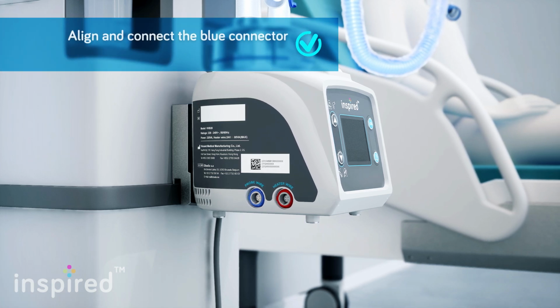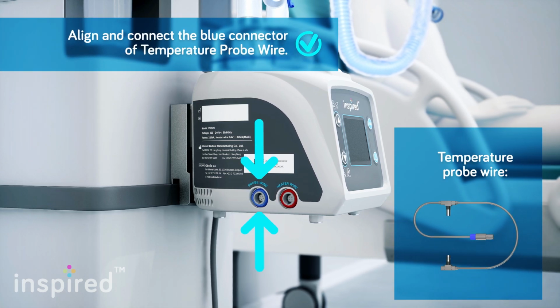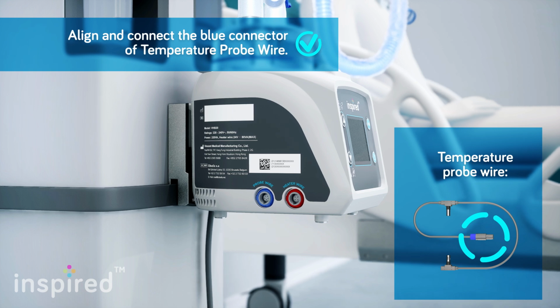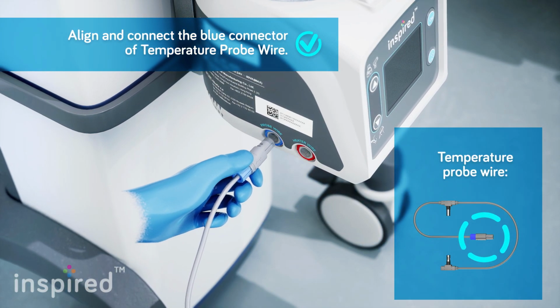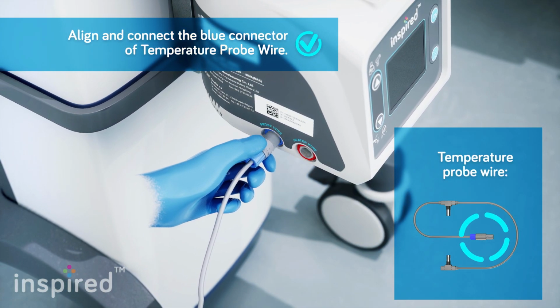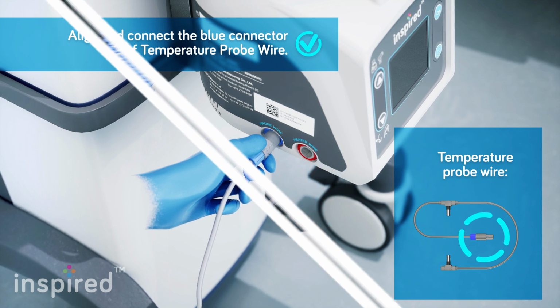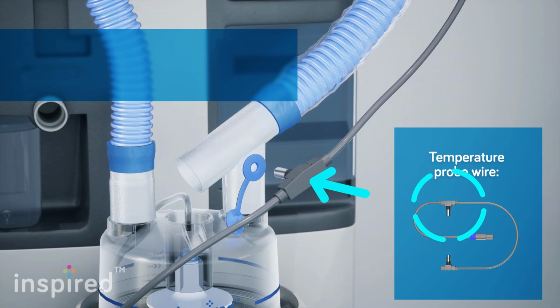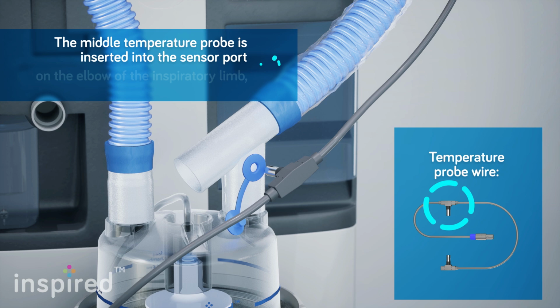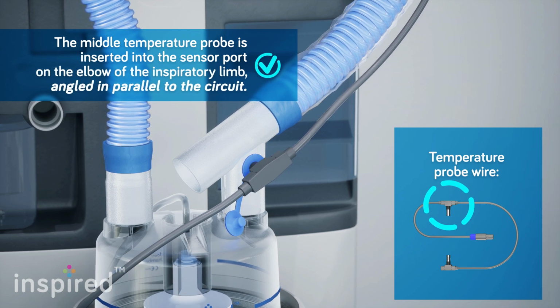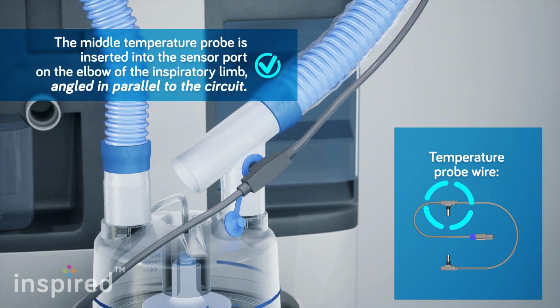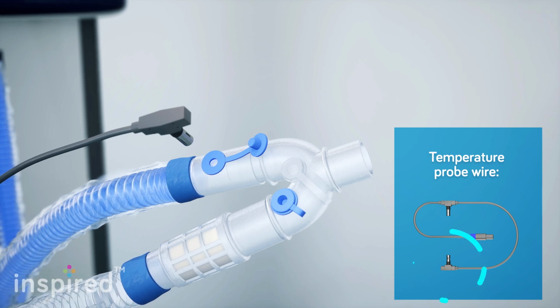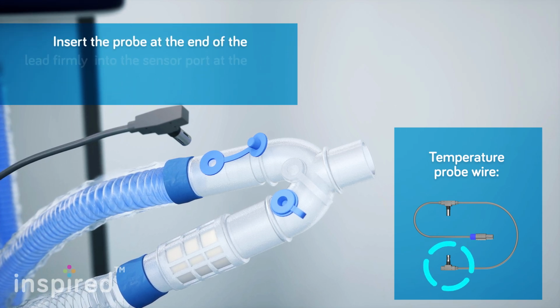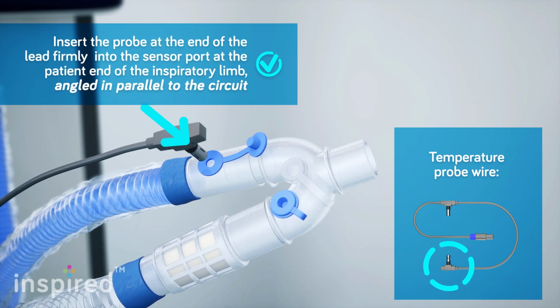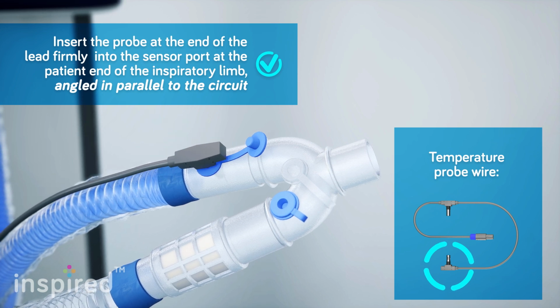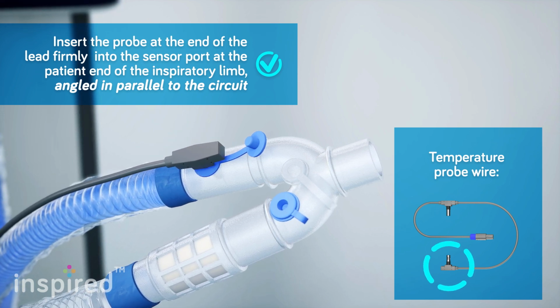Align and connect the blue connector of temperature probe wire into the blue socket found on the left side of the device. Secure the connection until a click sound. The middle temperature probe is inserted into the sensor port on the elbow of the inspiratory limb, angled in parallel to the circuit. Insert the probe at the end of the lead firmly into the sensor port at the patient end of the inspiratory limb, angled in parallel to the circuit.